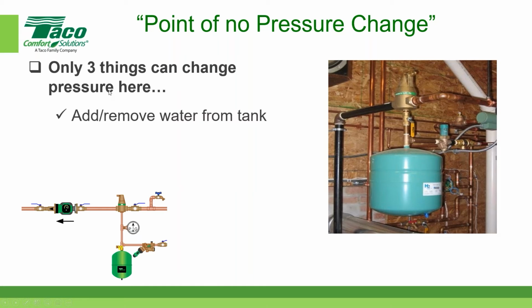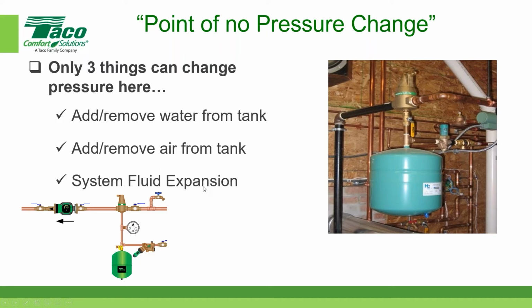So can I change the pressure there? Yes, add or remove water from the tank. That means if I let water in here with this assembly, that's going to change. If I add or remove air from the Schrader valve here or over here, this little blue thing, that's going to change that pressure gauge. Or if I light the boiler up, fire it up, and the system comes up in temperature, I'm going to change that gauge here. Now, you would say, well, you just showed me 3 things that are going to change the pressure at the point of no pressure change.